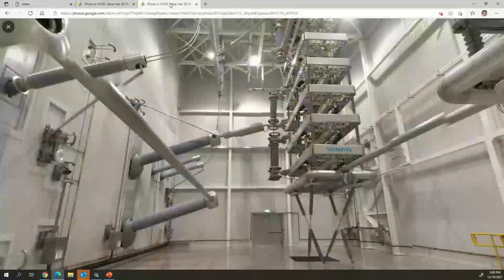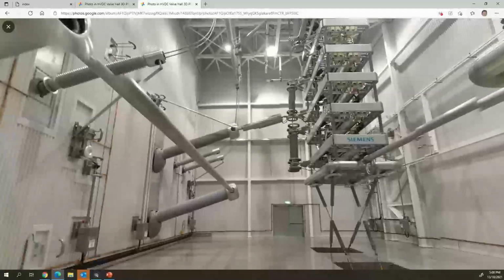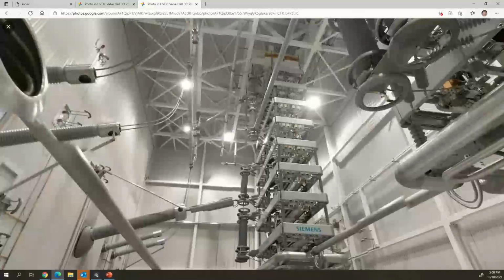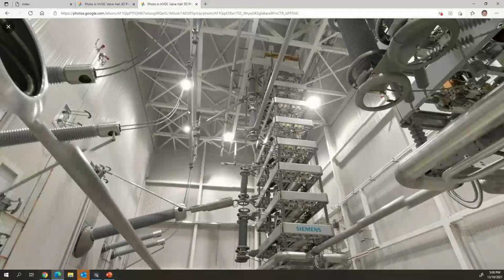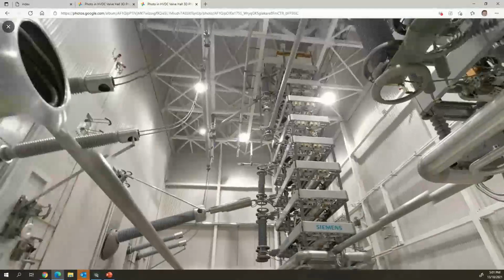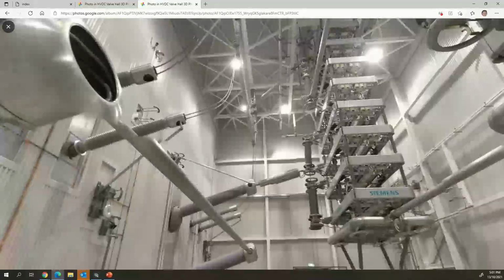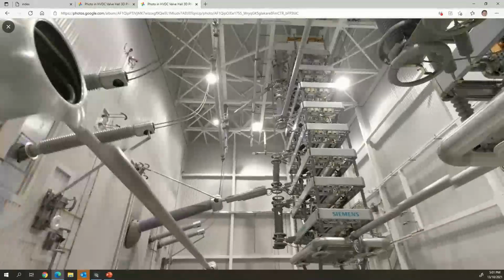This is the Siemens valve. See, it's quite a bit different than the ABB valve. They sort of have it around the other way. And the other key difference is that the delta connections are made inside the valve hall for pole 3, and for pole 2 they're made outside, and then they have bushings coming in. So the Siemens design has less bushings, but you do need a bit more room in the valve hall to make this delta connection up the top. But it's exactly the same design, really. I mean, 30 years newer, but it's the same circuit diagram.